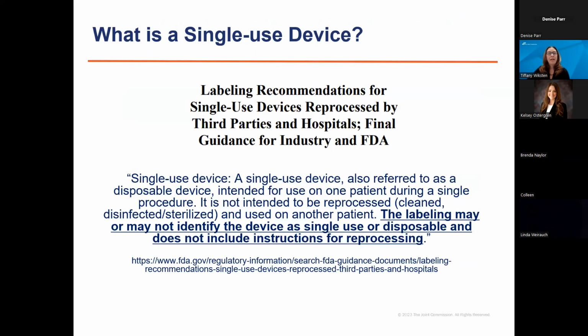So again, what is a single-use device? And I like this little slide here because the part that's underlined isn't necessarily true as we're finding it anymore, right? The labeling may or may not identify the device as single-use or disposable and does not include instructions for reprocessing, but some of them do include instructions for processing them prior to use. So if you're unsure if an item is single use or reusable, contact the manufacturer for clarification and obtain their response in writing. It's really, really, really important.